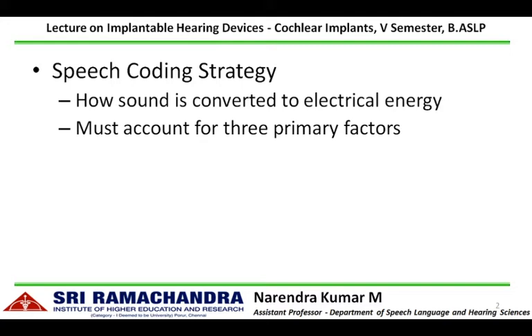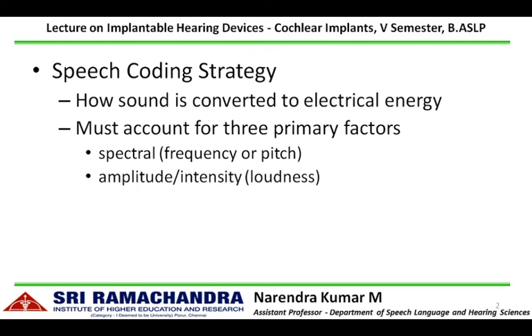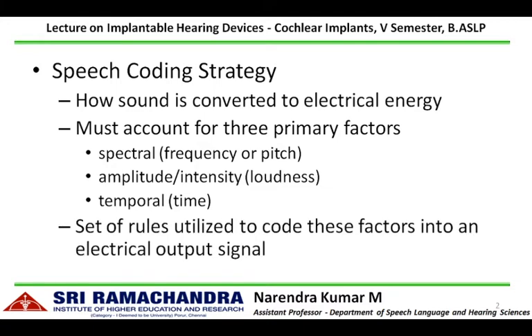The processed signal is given to the electrode array to stimulate the auditory nerves in the cochlea. This information must account for three primary factors of the incoming signal: the spectral information, which includes the frequency composition; the amplitude or intensity, which contributes to loudness perception; and the temporal information, which is the time-varying component showing how the signal varies across time. The set of rules used to code these factors into an electrical output signal is called a speech coding strategy, which is an algorithm stored in the speech processor.